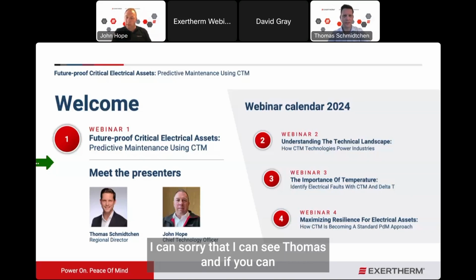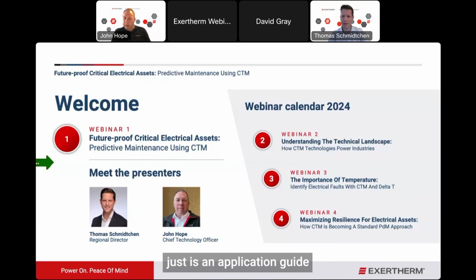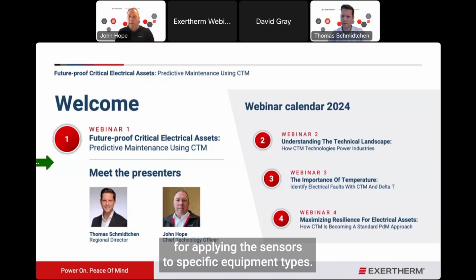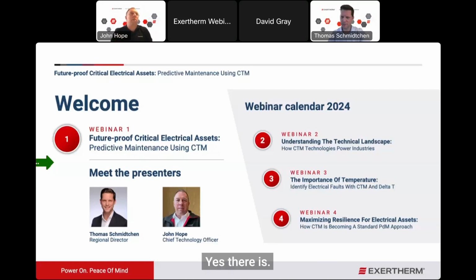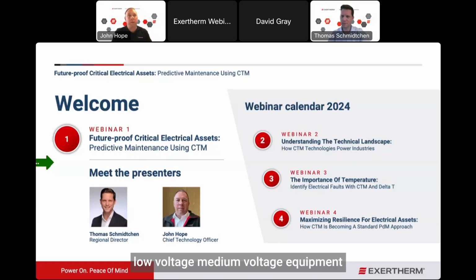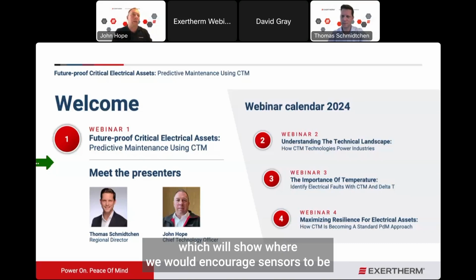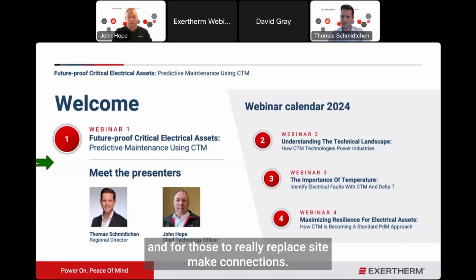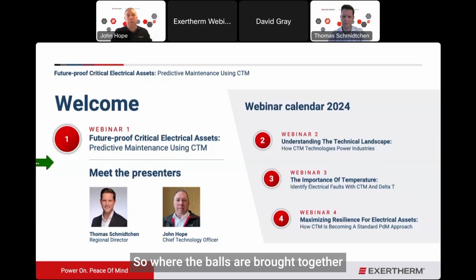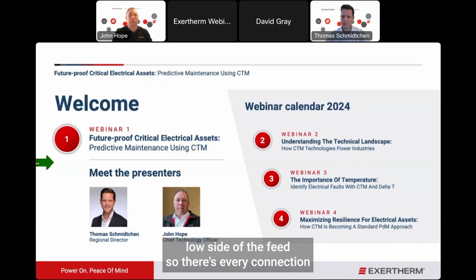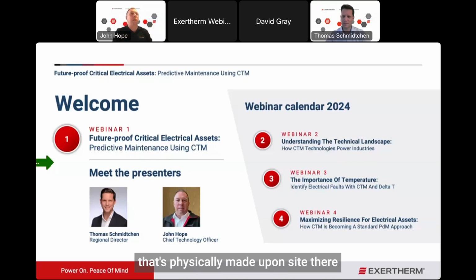I think another one that I can see, Thomas, and I don't know if you can. You've asked, is there an application guide for applying the sensors to specific equipment types? Yes, there is. We have guides for low voltage and medium voltage equipment, which will show where we would encourage sensors to be. And for those two, really, it's site-made connections. So where the boards are brought together on site from transport, shipping, split, line side of incomers, load side of the feeders. So it's every connection that's physically made up on site.